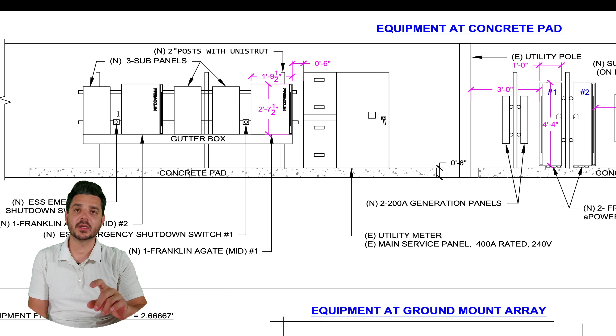Now, what we did with the batteries over here, we needed to consolidate space. So this is a utility pole coming in next to the service equipment. So power is overhead, but then it comes down the pole and then it goes into the 400 amp service. So what we've done here is we've rotated the aPowers. So instead of them all just being stacked across each other and being really long, because this would be excessively long. It's already pretty long with the 3-foot gap that we need to put in front of each one. But we don't need to double up. Per the NEC, we can have equipment facing each other, and you can have 3 feet in 3 feet because you're only going to work on one unit at a time.